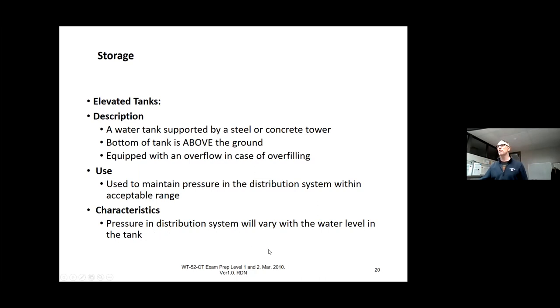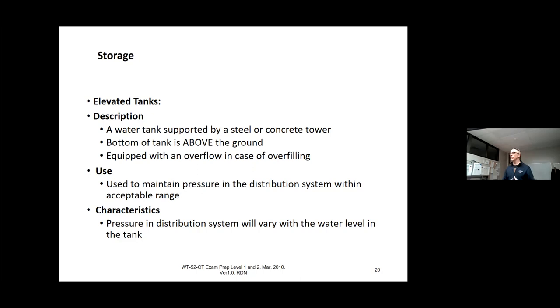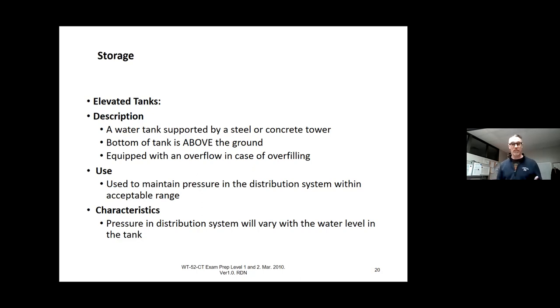One important thing about pressure: the distribution system pressure will vary with the water level in the tank. Level is equal to pressure — if you have more water in your reservoir, you're going to have more pressure. That is really important: level is equal to pressure, always.